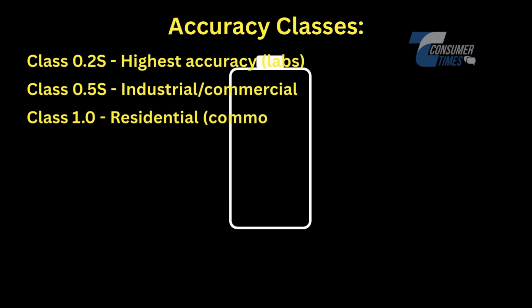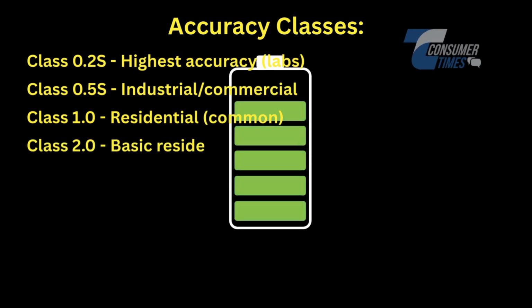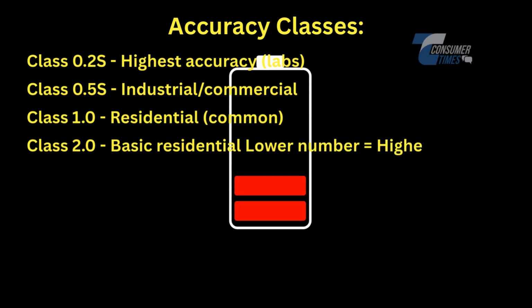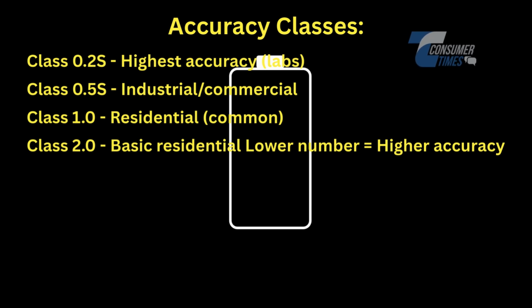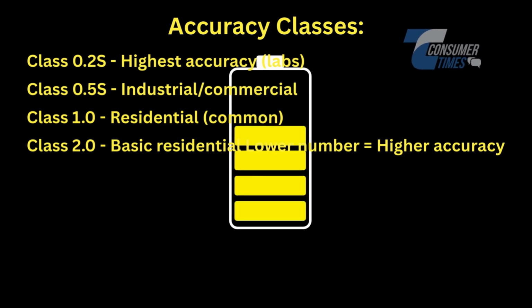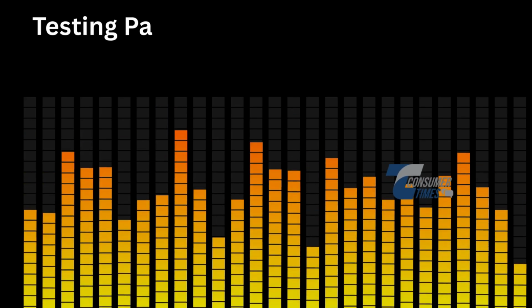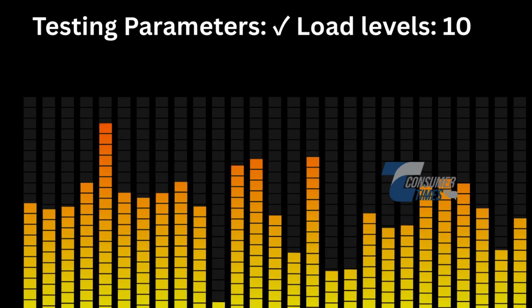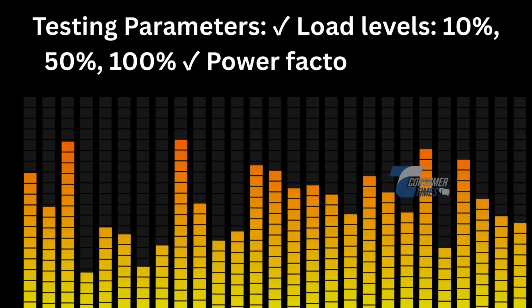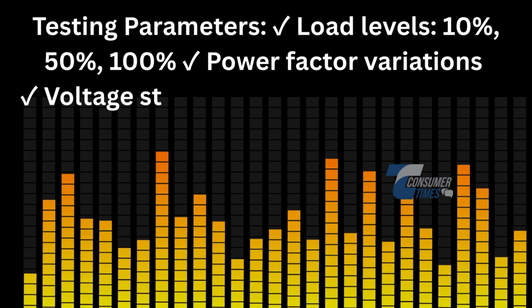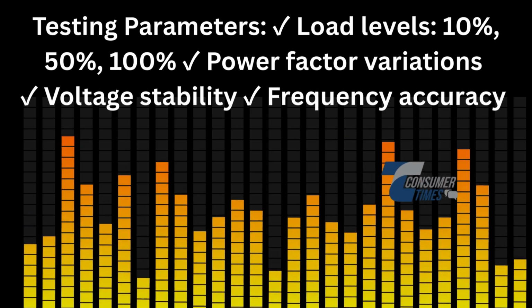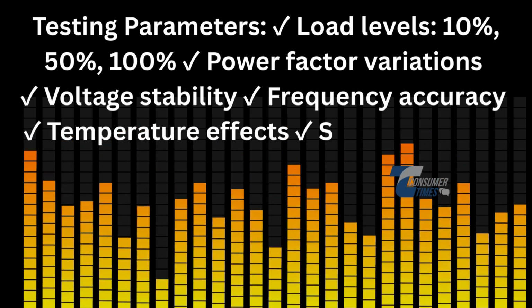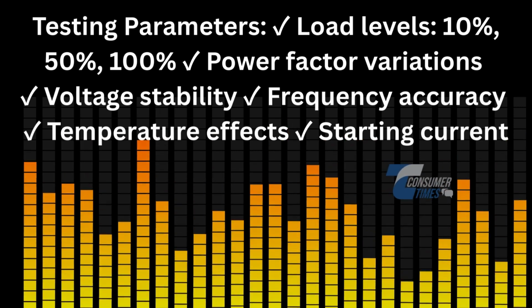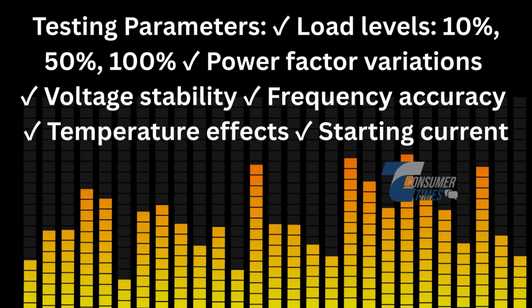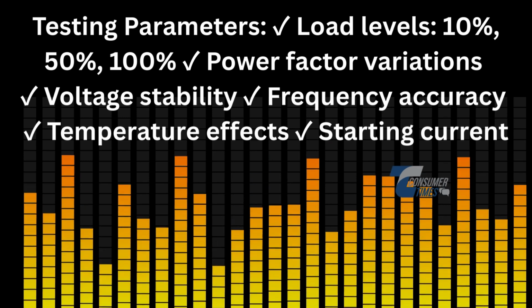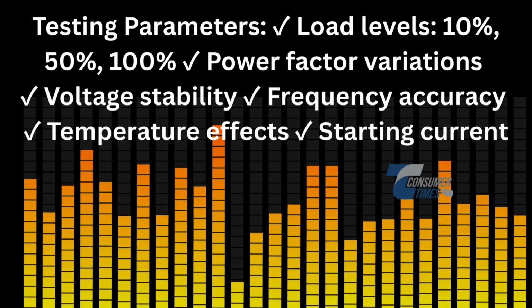meters. In India, we follow the Bureau of Indian Standards specifications, particularly IS 13779 for alternating current static watt-hour meters and IS 16444 for electronic meters with additional functionalities. These Indian standards are harmonized with IEC standards to maintain global compatibility. In North America, the American National Standards Institute standard ANSI C12.20 governs revenue metering, providing specifications for accuracy classes and testing procedures. These standards aren't just technical documents, they're your protection as a consumer. They define exactly how accurate a meter must be, how it should be tested, and what tolerances are acceptable.